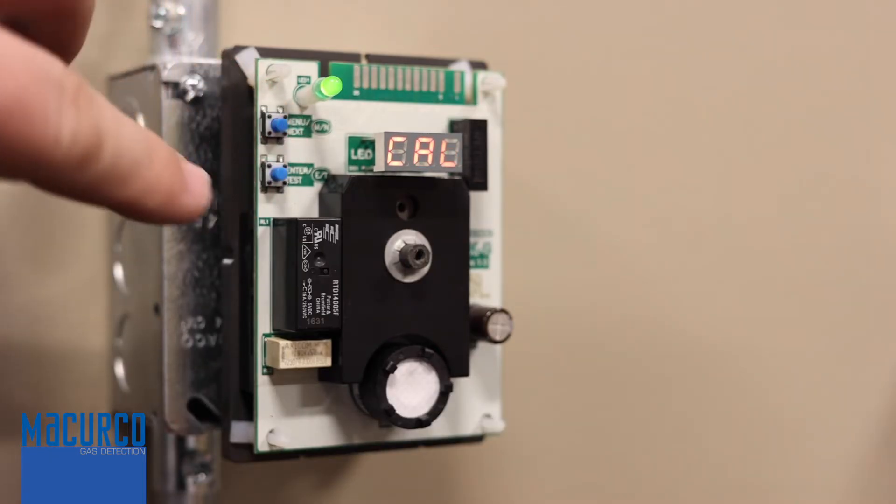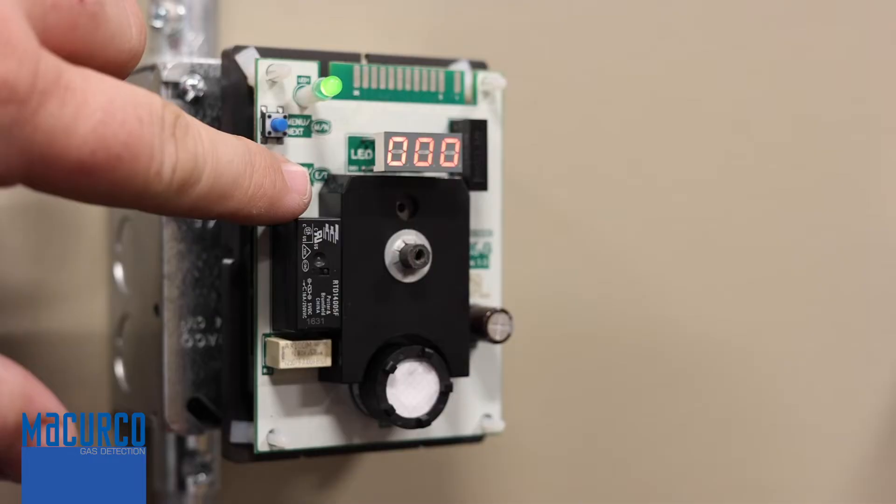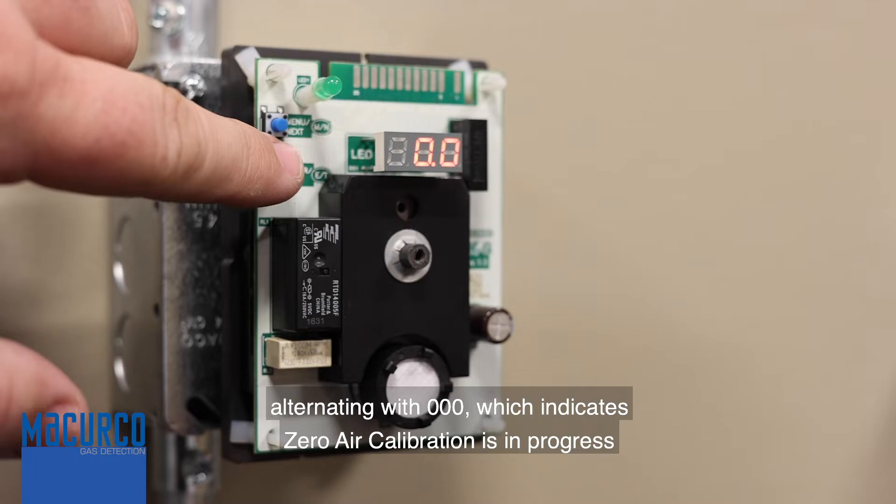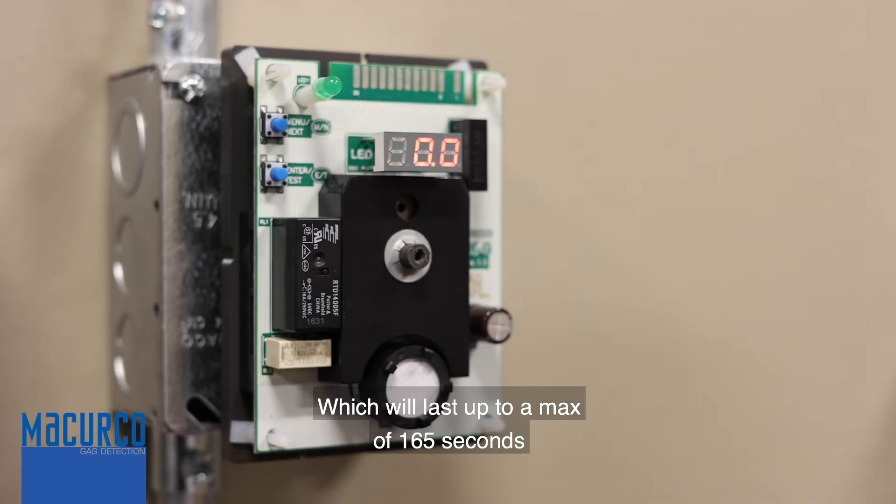Then press the enter button to get to zero zero zero or calibration zero mode. Press the enter button and the display will read 0.0 alternating with zero zero zero, which indicates zero air calibration is in progress, which will last up to a max of 165 seconds.